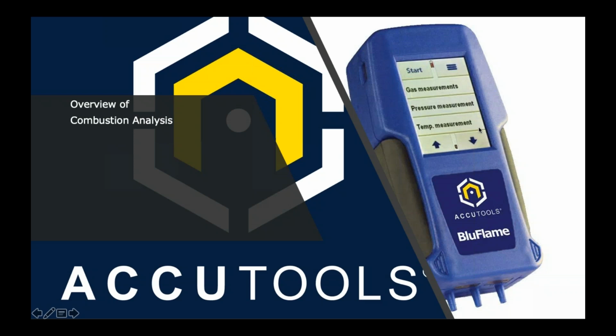A lot of people don't think about the versatility of a combustion analyzer and what it can do, and they think it's just a one-shot wonder. It just measures combustion, and it does so much more. It's almost the only tool that you need to set up a furnace properly, because you can do your ambient CO testing, your incoming gas pressure, your manifold pressure, temperature rise, total external static pressure, pressure drop testing across filters and coils. You can do all your combustion testing of a furnace, hot water tank, stoves, ovens, dryers, draft testing, CAZ testing, and other things. It's not just a single simple instrument. It does way more than most people realize, and it's got some really high-end sensor technology when it comes to temperature and pressure, and it makes the setting up of a furnace much, much easier.